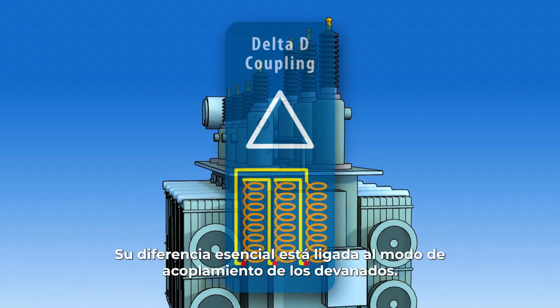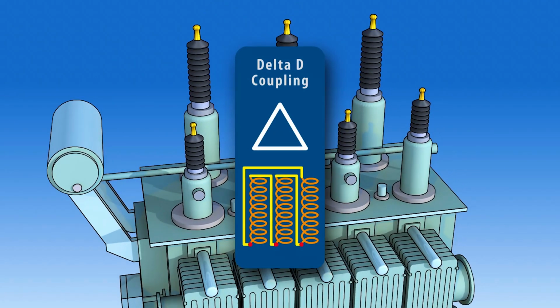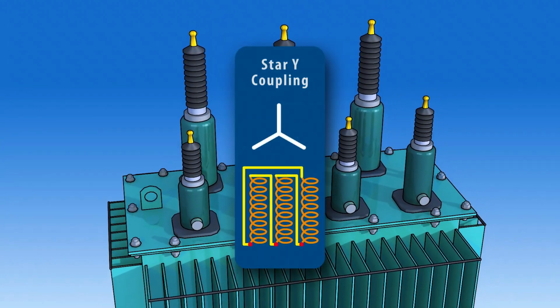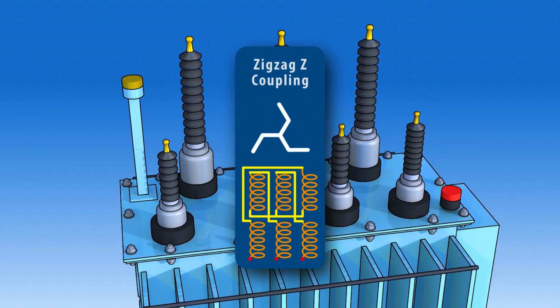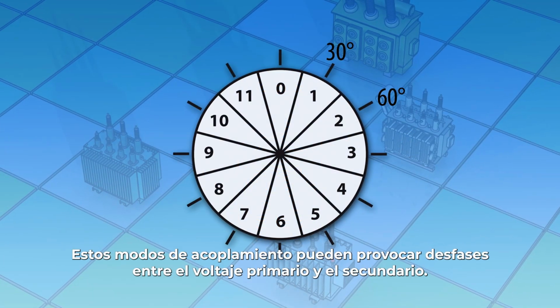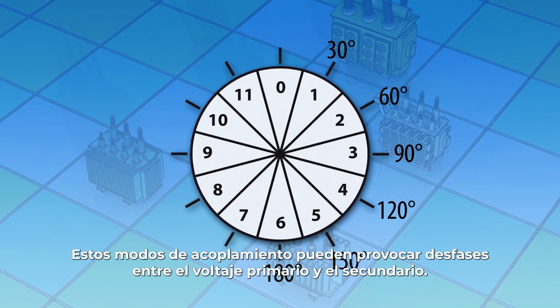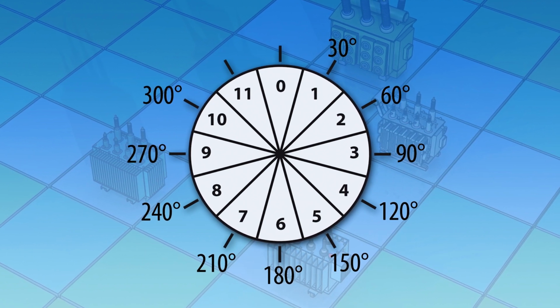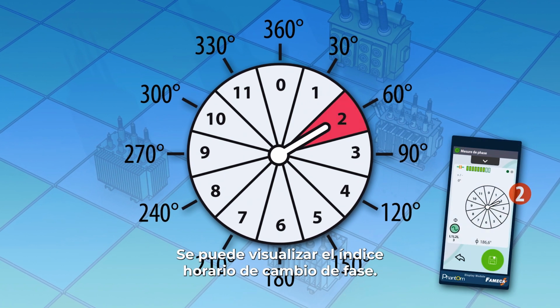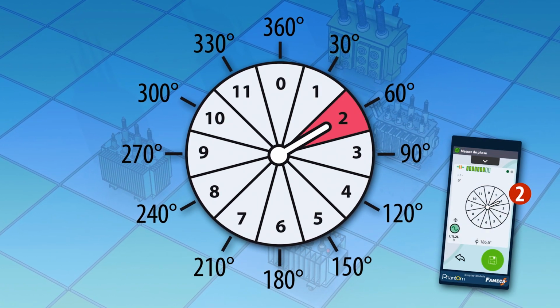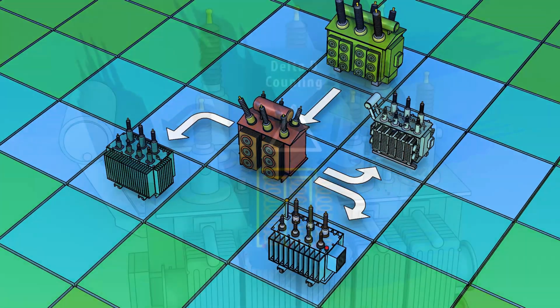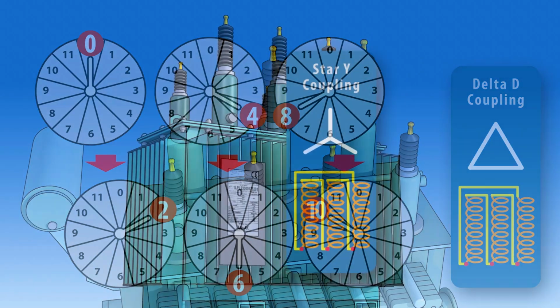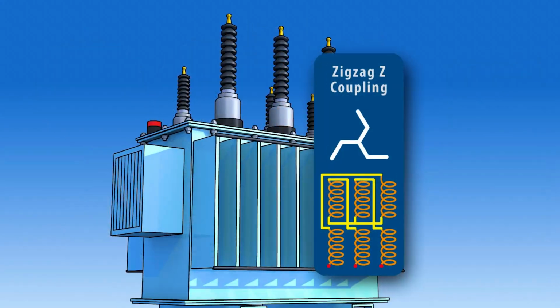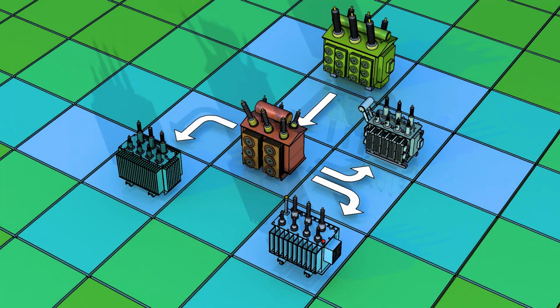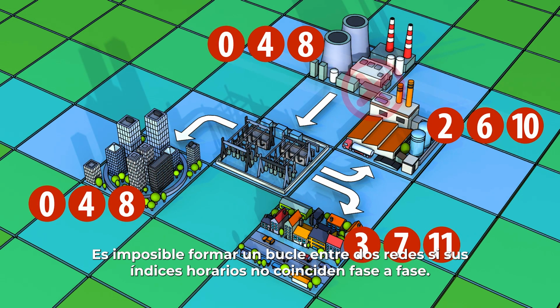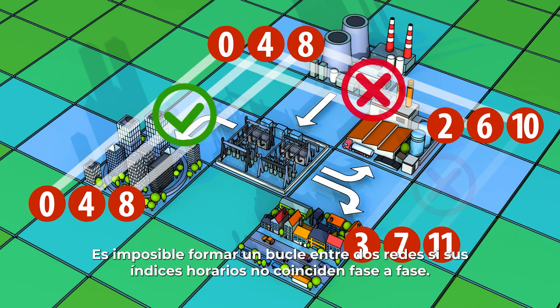Their essential difference is linked to the mode of couplings of the windings: the triangle coupling, the star coupling, the zigzag coupling. These coupling modes can cause phase shifts between the primary voltage and the secondary voltage. These phase shifts are measured in degrees. An angle of 30 degrees corresponds to 1 hour on a clock. The phase shift time index can be displayed. It is impossible to loop two networks if their time indexes do not match phase to phase.